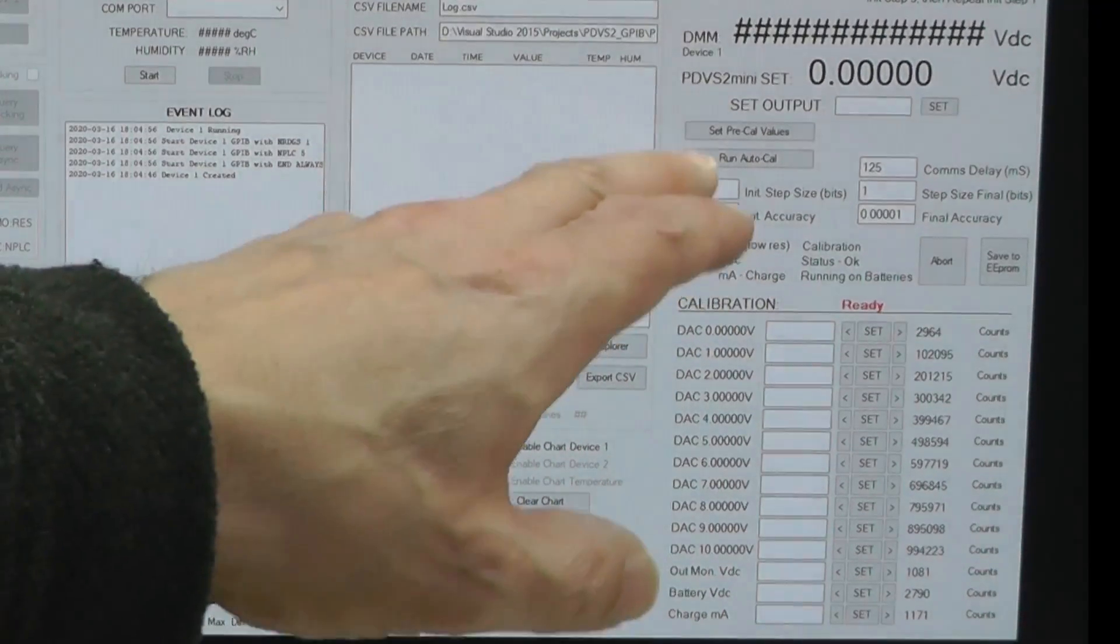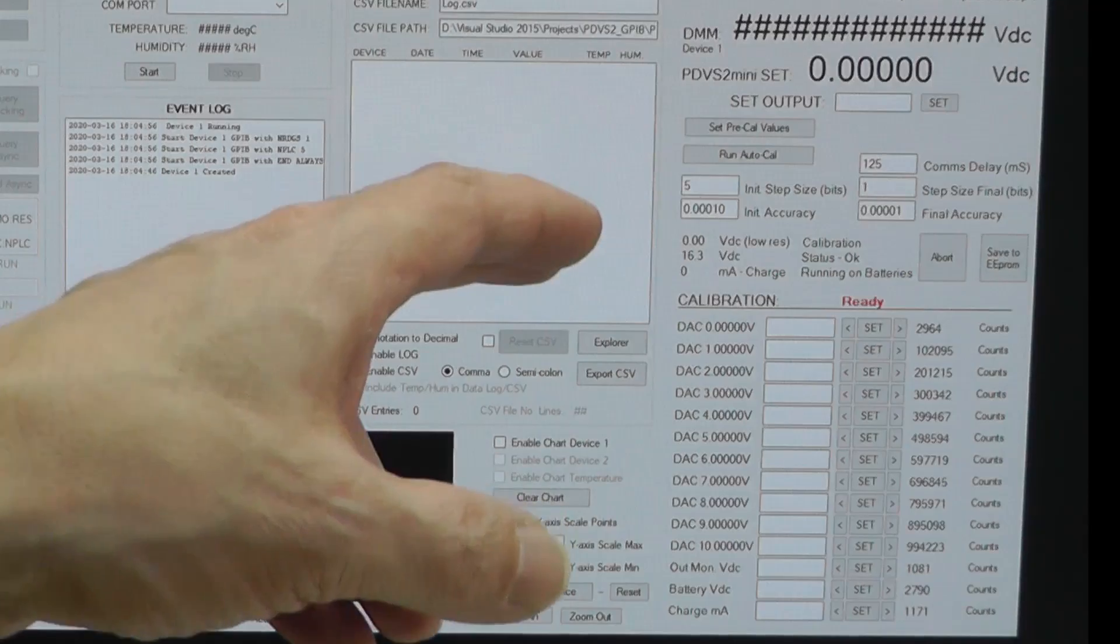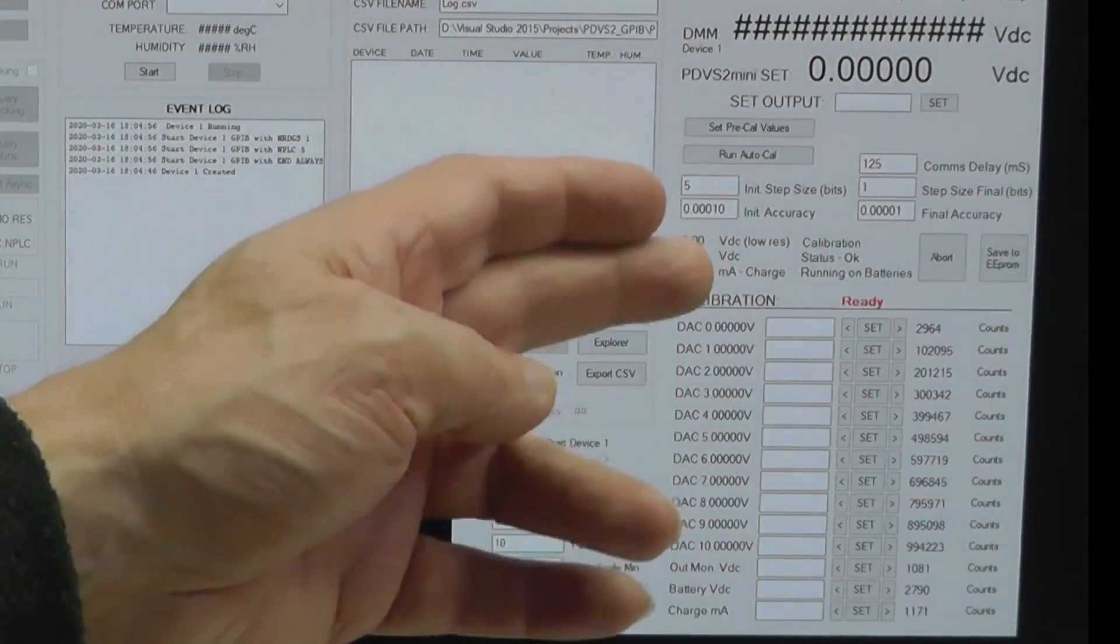...and the idea is that I start off this app at this right hand side here and run the calibration. So the first thing I would do is send pre-cal values to the PDV-S2 mini. What's that all about? Well if there's virtually no calibration data at all in the PDV-S2 mini then the way this will work would be quite slow, it would take forever to step up or step down to the final value. So what I'm able to do is pre-load the PDV-S2 mini with numbers that I've gotten historically from previous calibration, previous manual calibration that I've done over the past couple of years. So I'll load those as default values in first and then when I run the auto calibration that's the starting point.